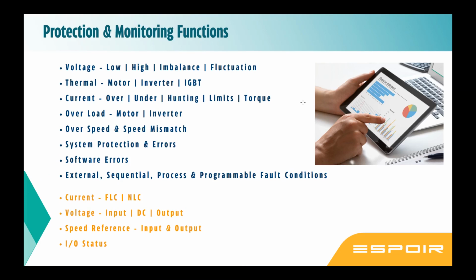A star delta starter, DOL starter, conventional starters, don't have a protection for this. It runs. So in many cases, in rural sites where the power quality is poor or at peak time, there is always the issue that, sir, your VFD is tripping, our other motor is running, because the other motor doesn't have any sensor. It doesn't sense any of the voltage parameters, so it runs. You cannot compare it with an electronic device, which is a VFD. It senses everything. Some customers find this a nuisance trip, but it is to protect the system, so they need to work hard to address the electrical parameters.